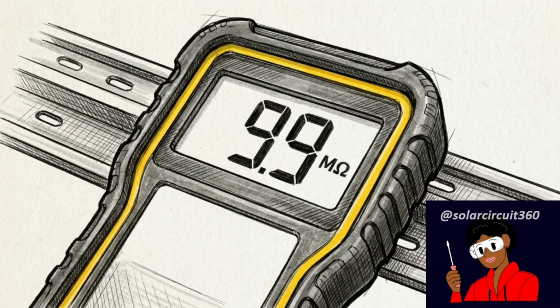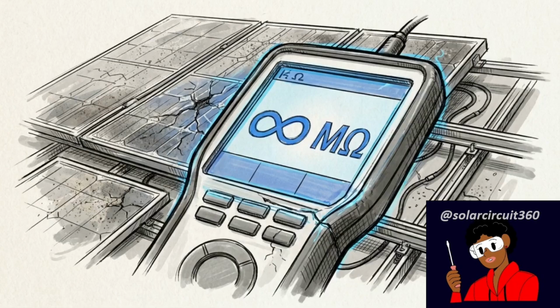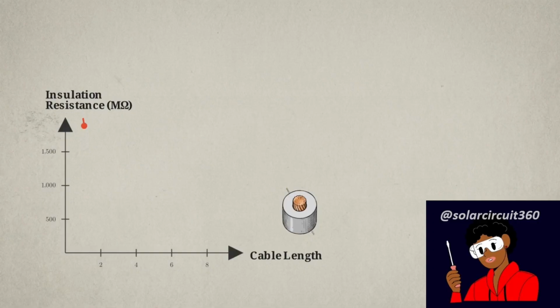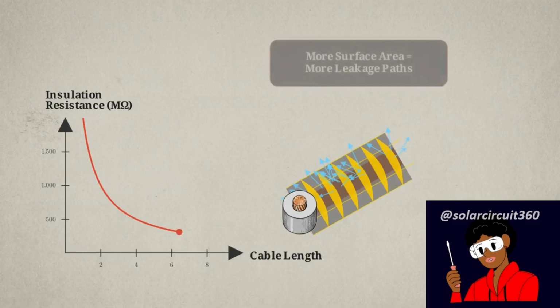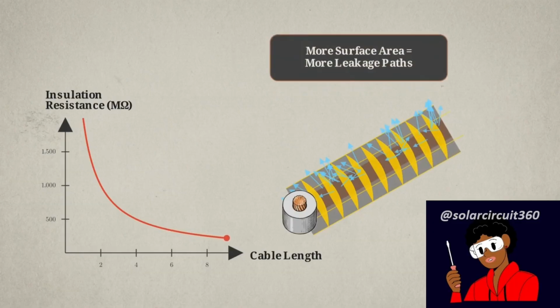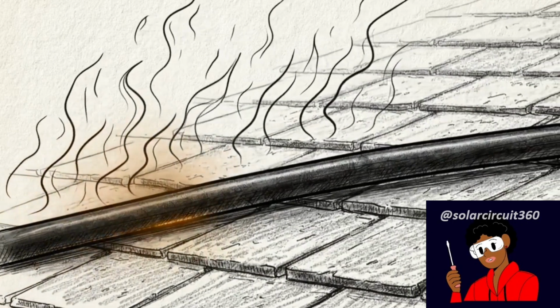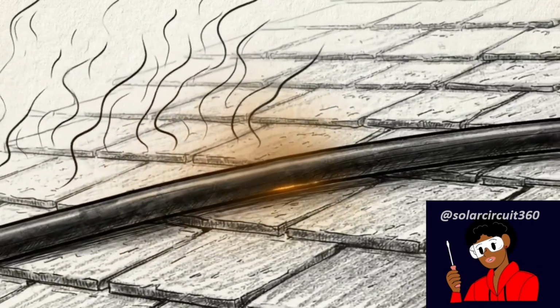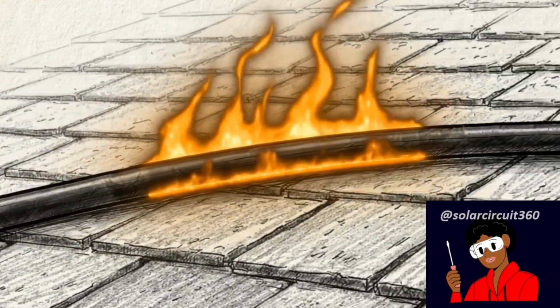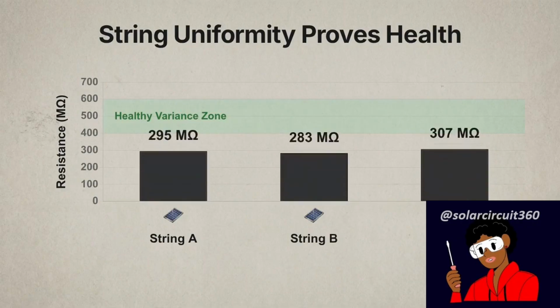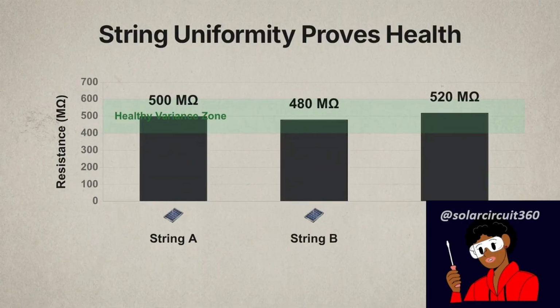A common misconception in solar maintenance is that any reading below 100 megaohms is a failure, and that healthy systems must always show infinite resistance. In reality, insulation resistance is tied directly to the total physical length of the cable run. As cable length increases, measured resistance naturally decreases. A longer cable has more surface area, creating more baseline paths for microscopic leakage current to flow. Variations in wire gauge and cable temperature also influence these readings, shifting the baseline for what counts as a normal measurement. Effective diagnostics rely on tracking relative degradation and performing string-to-string comparisons rather than searching for a universal magic number.